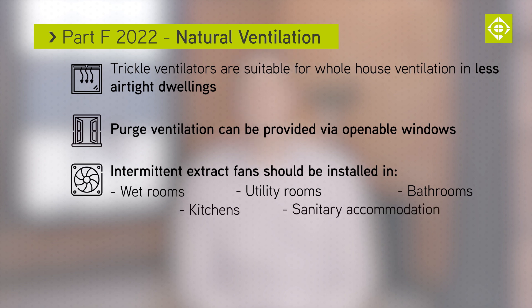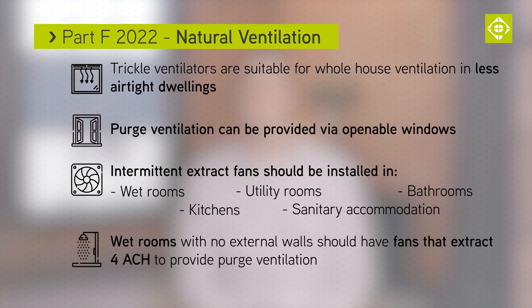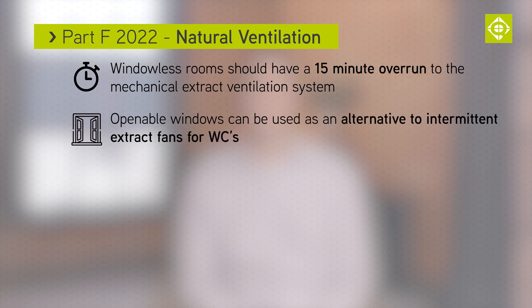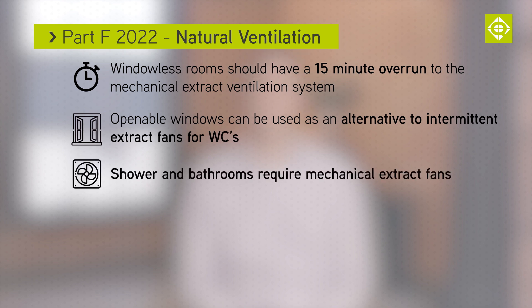Wet rooms with no external walls should have fans that extract four air changes per hour to provide purge ventilation. Windowless rooms should have a 15-minute overrun to the mechanical extract ventilation system. Openable windows can be used as an alternative to intermittent extract fans to WCs; however, showers and bathrooms still require mechanical extract fans.